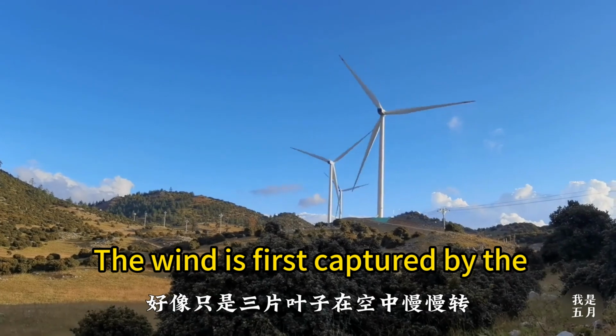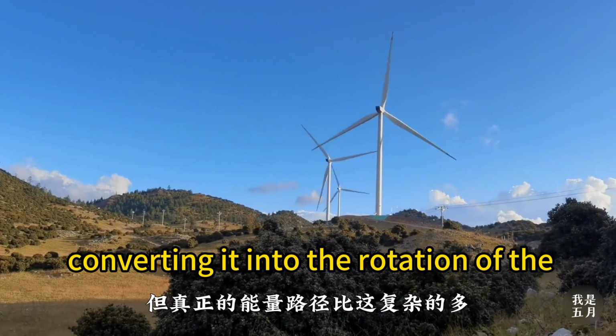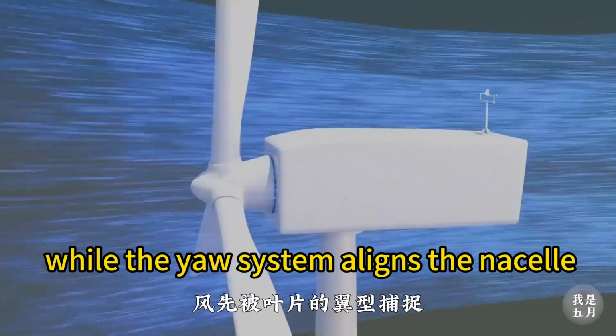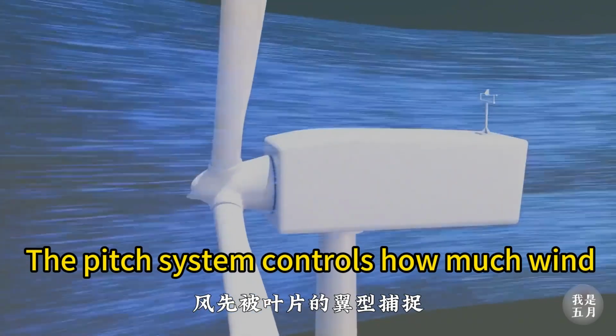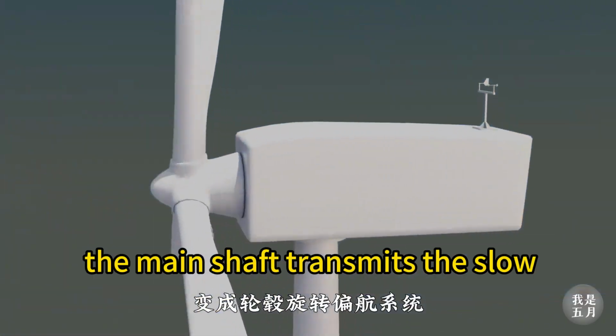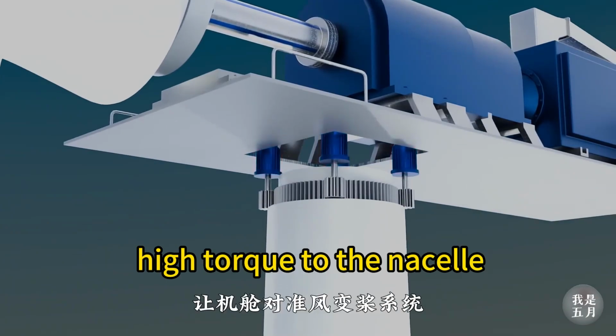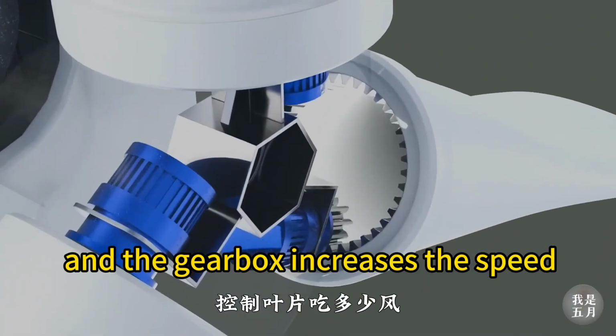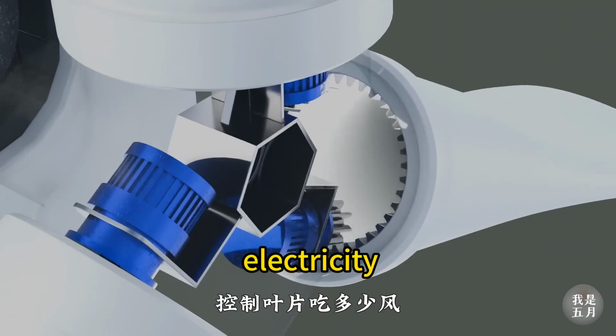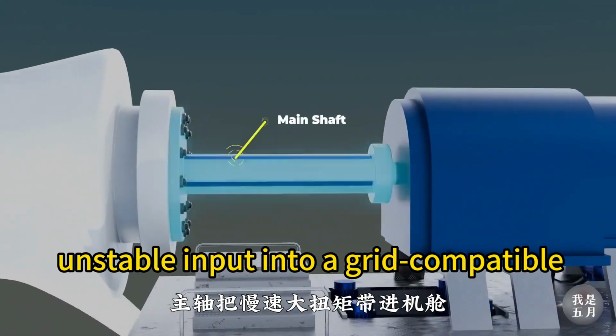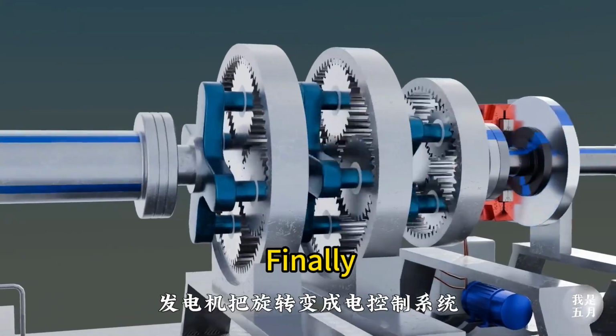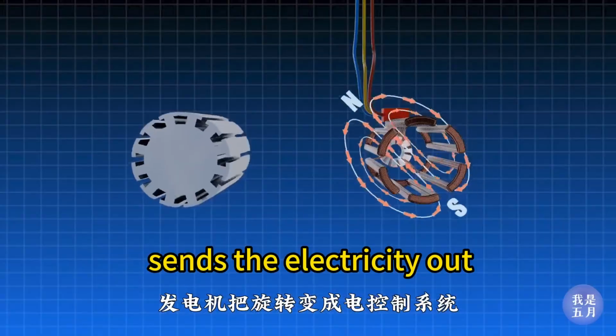The wind is first captured by the special shape of the blades, converting it into the rotation of the hub, while the yaw system aligns the nacelle with the wind. The pitch system controls how much wind the blades absorb. The main shaft transmits the slow, high torque to the nacelle, and the gearbox increases the speed. The generator converts rotation into electricity, and the control system corrects the unstable input into a grid-compatible output. Finally, the transformer boosts the voltage and sends the electricity out.